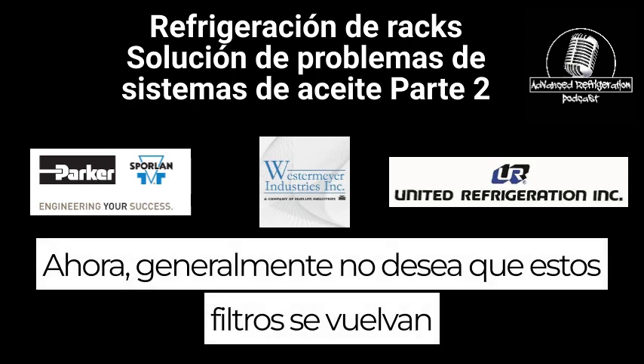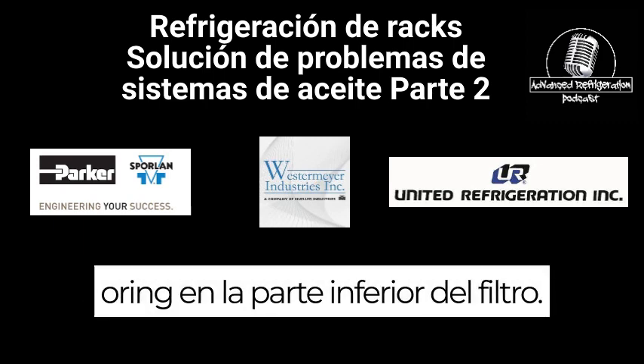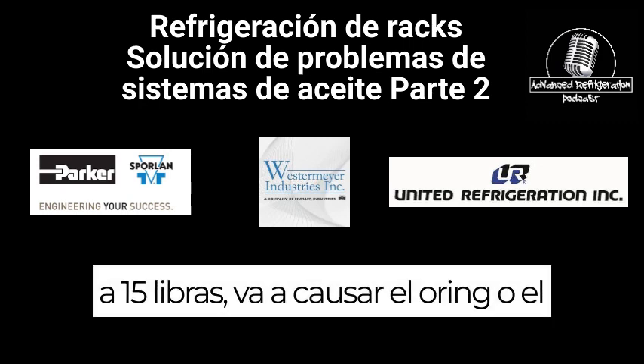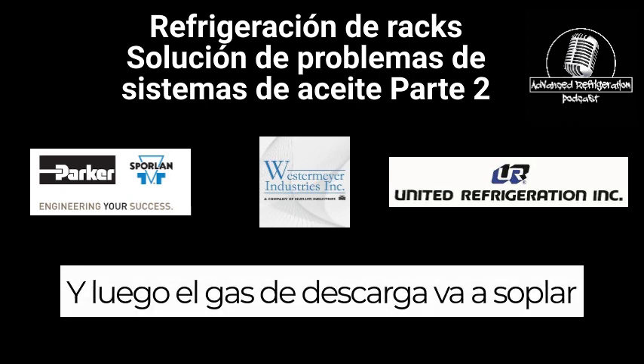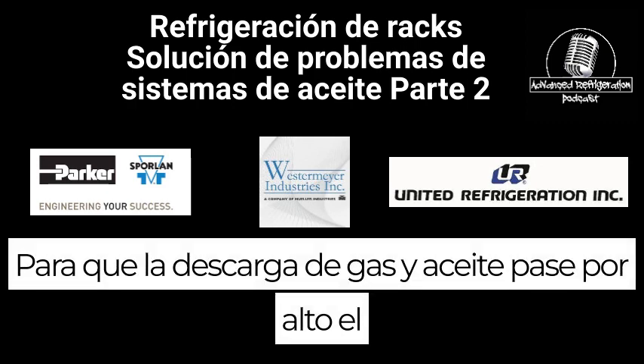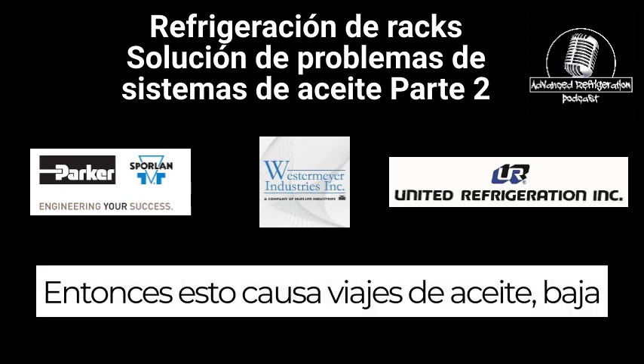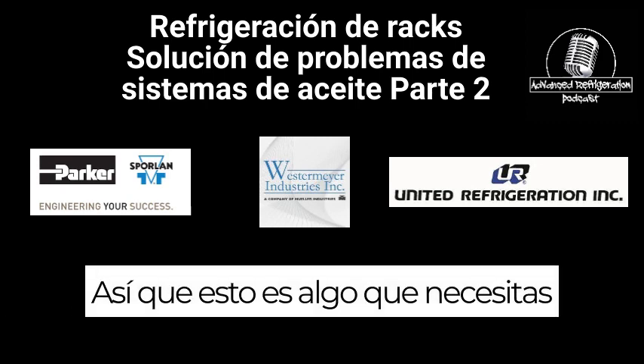Generally, you don't want these filters to get above 13 to 15 pounds or they blow the O-ring on the bottom of the filter. So as the differential across the filter gets above 13 to 15 pounds, it's going to cause the O-ring or the gasket on the bottom of the filter to fail. And then discharge gas is going to blow out around the bottom of the filter and not go through the filter and aerate. So that discharge gas and oil bypasses the filter and then goes out to the condenser. So this causes oil trips, low oil production out of the separator. So this is something you need to look at.